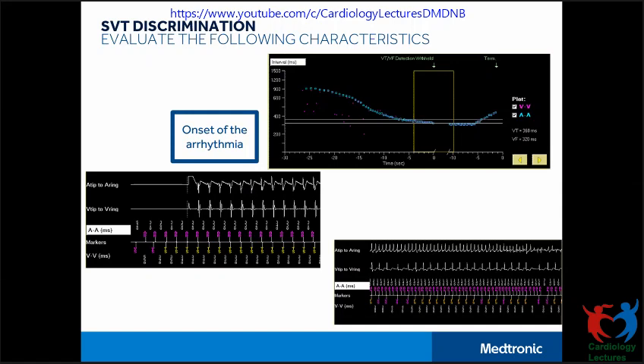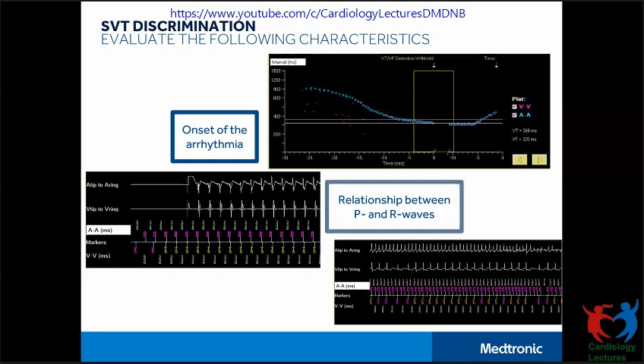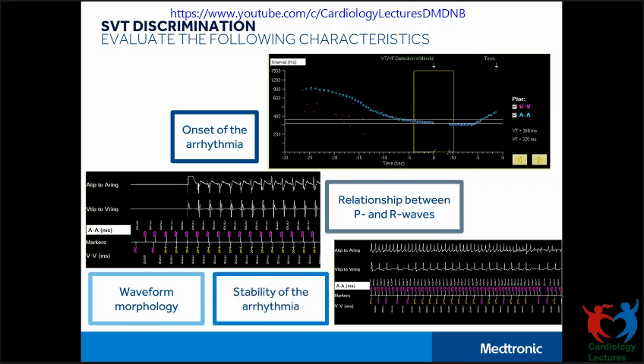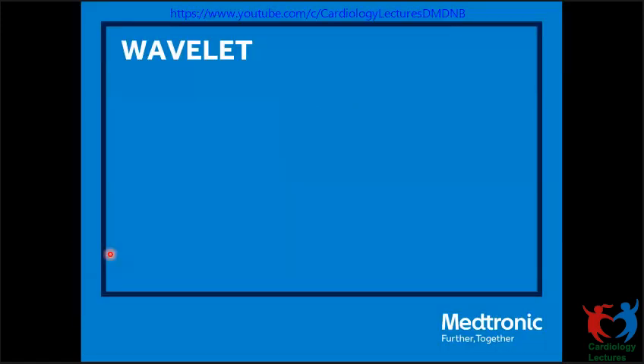The SVT discriminator evaluates the following characteristics: the nature of the onset of the arrhythmia, the relationship between the P and R waves, the waveform morphology, and the regularity of the arrhythmic rate. All four discriminators are available in the dual chamber ICD as well as CRTDs. In the single chamber ICD, all are available except PR Logic. Let's first start with Wavelet.